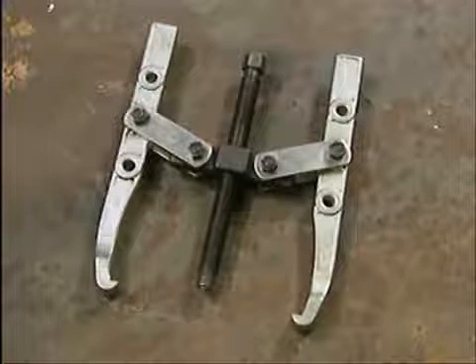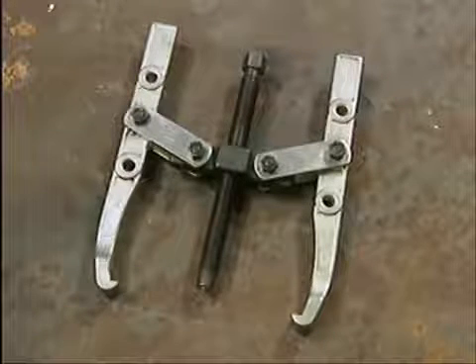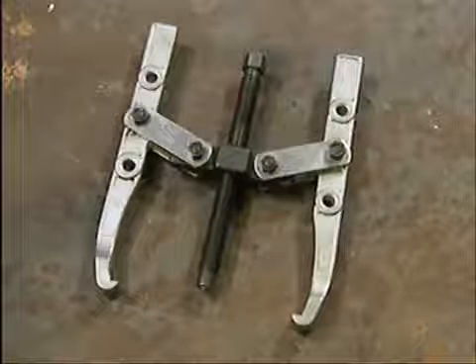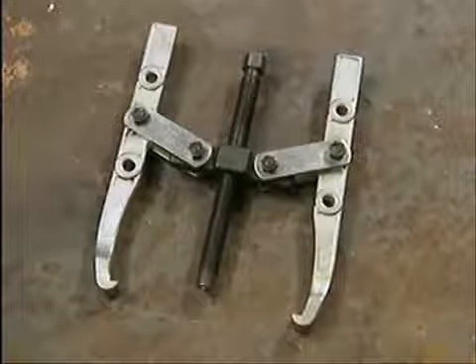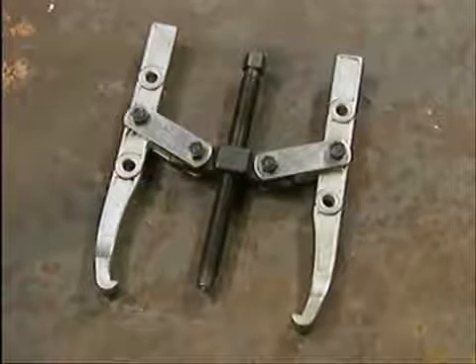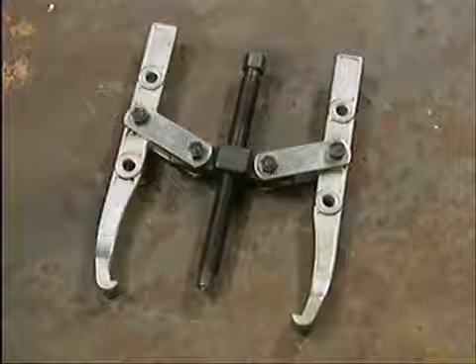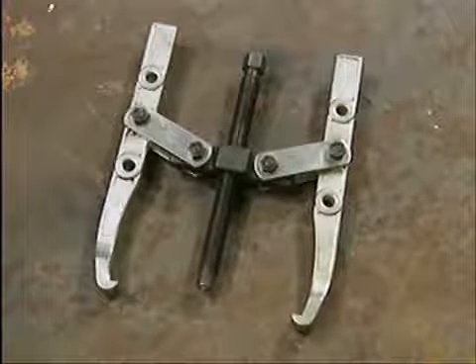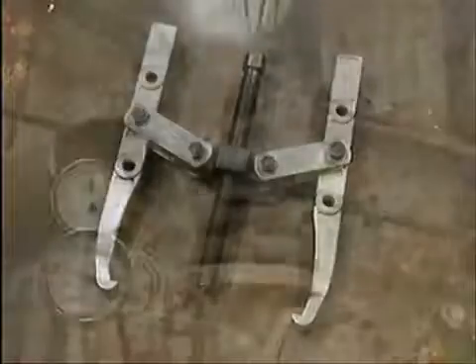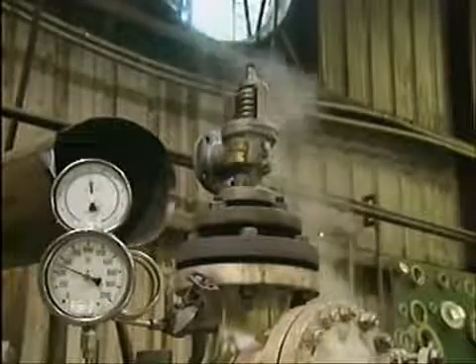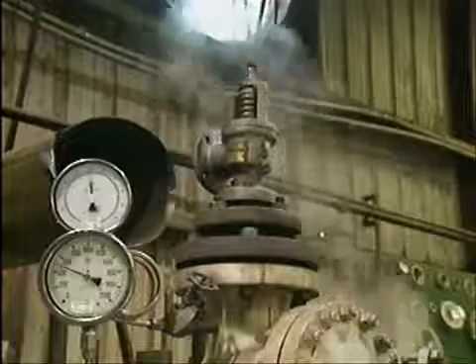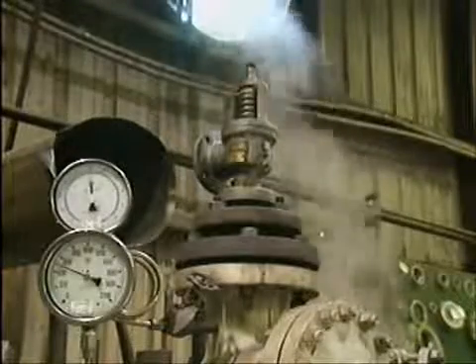Next, prepare to perform the necessary tests. An important preparation for many testing procedures is gagging the valve. Gagging involves installing a device called a gag that keeps the safety valve from opening during testing. We'll look at a typical procedure for installing a gag on a two-ring huddling chamber safety valve.